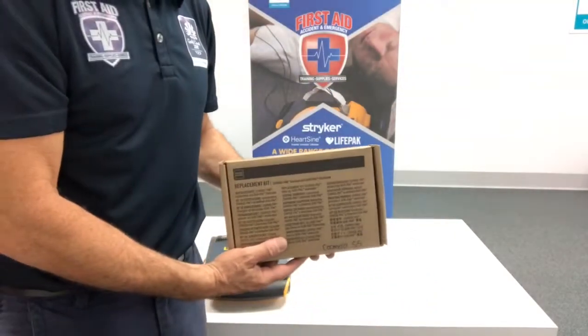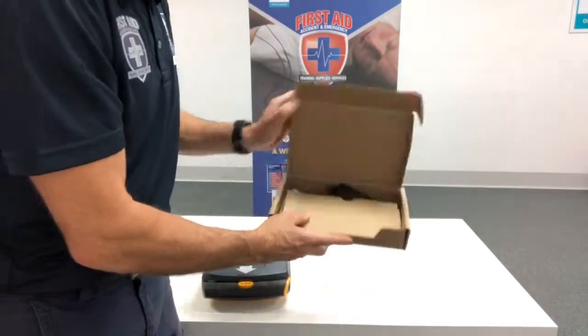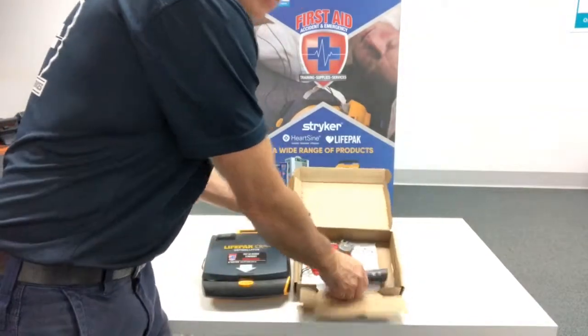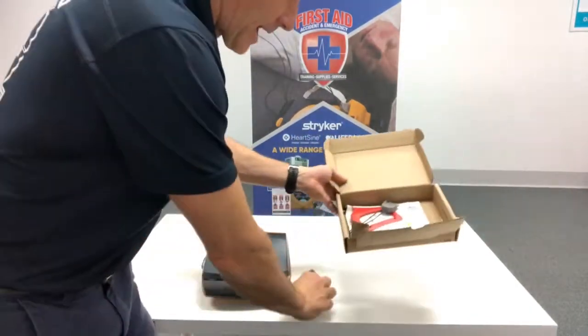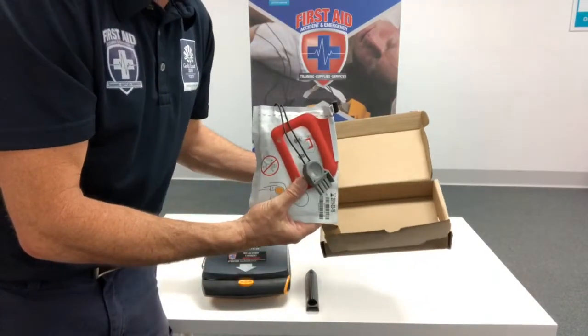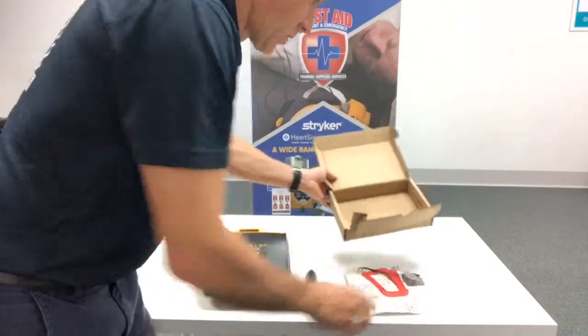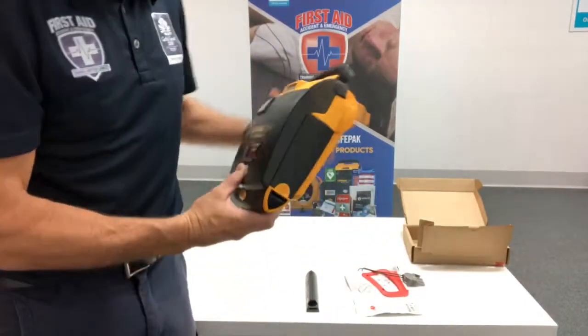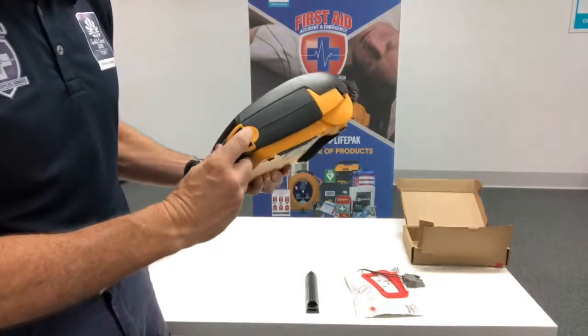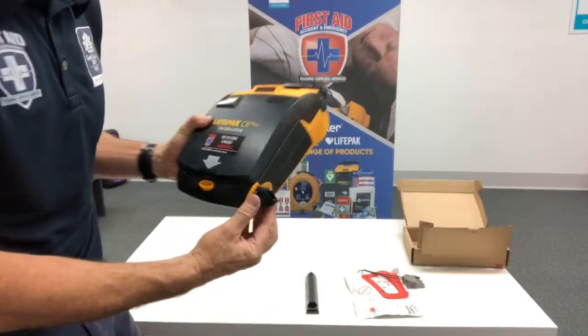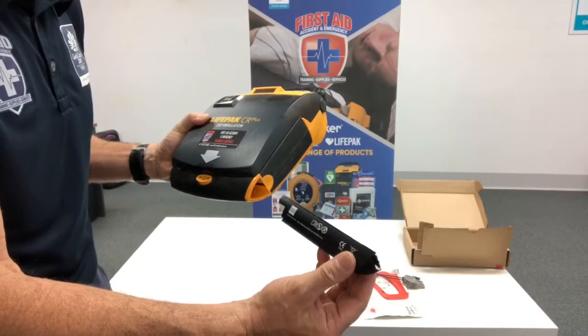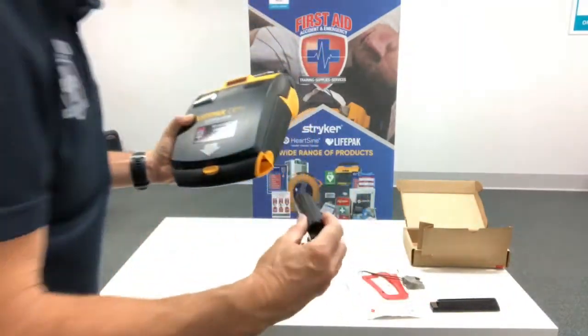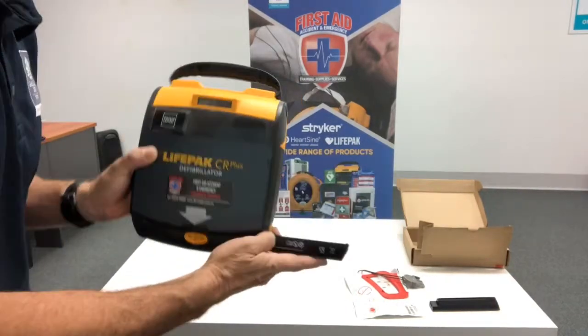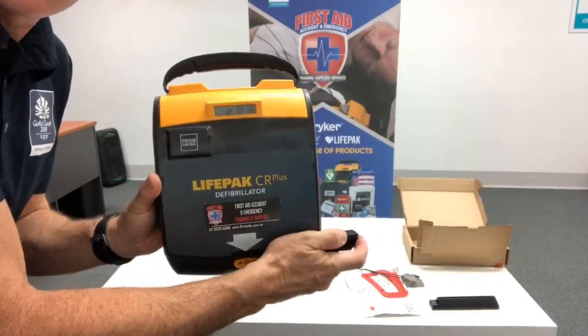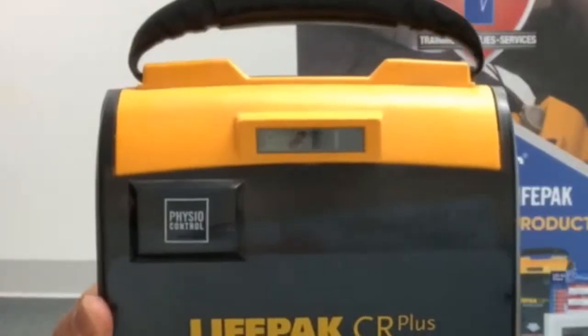Once you receive your pad and battery pack, quite simply open up the pack, and what you'll find in here is a replacement trickle charge battery and the replacement pads for your CR Plus defibrillator. Quite simply, on your defibrillator, on the bottom right hand side, there is a small clip that you take out the trickle charge battery. This is the old one, and then we replace it with a new trickle charge battery. Now what you'll notice as well is when we do this, see the top 3 dots on the top? This will now change to OK on your device.